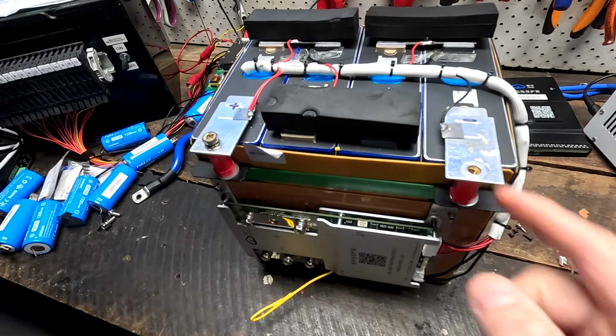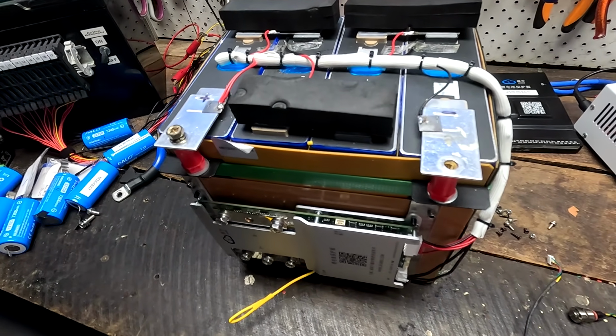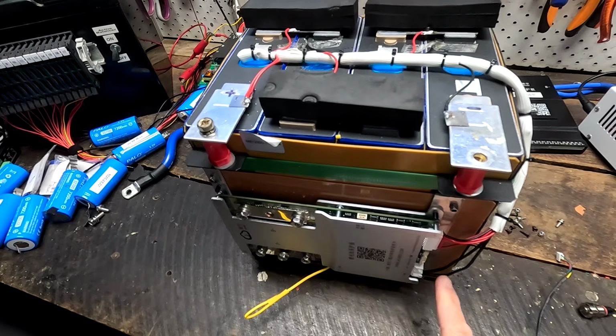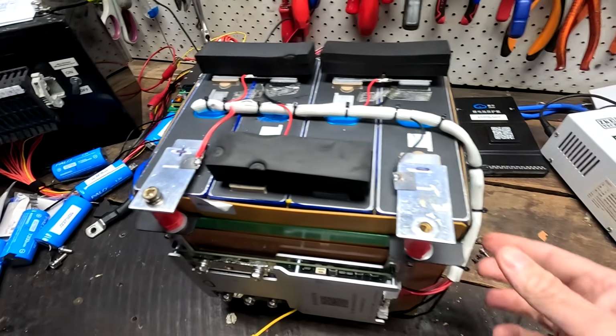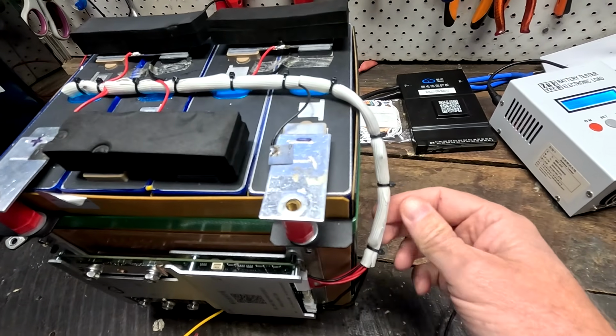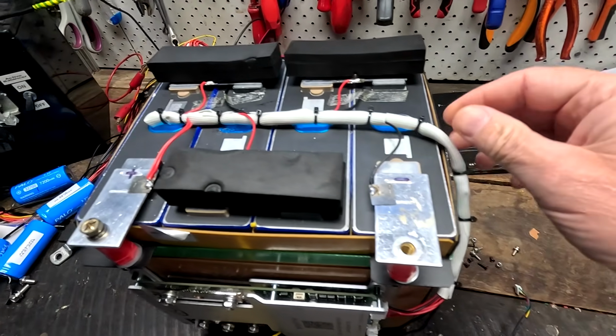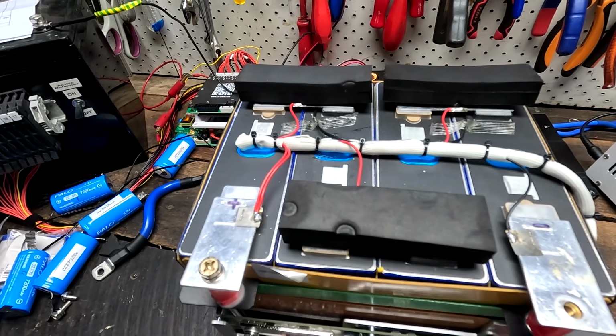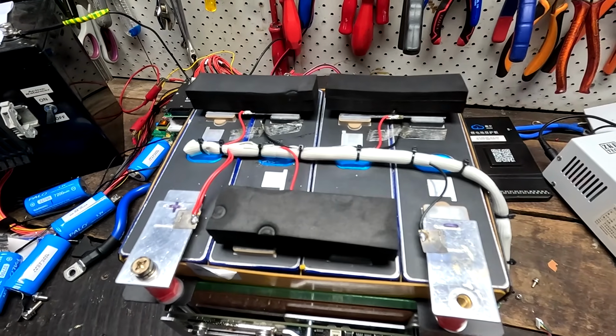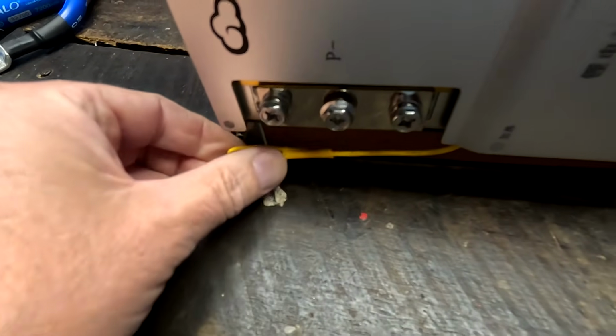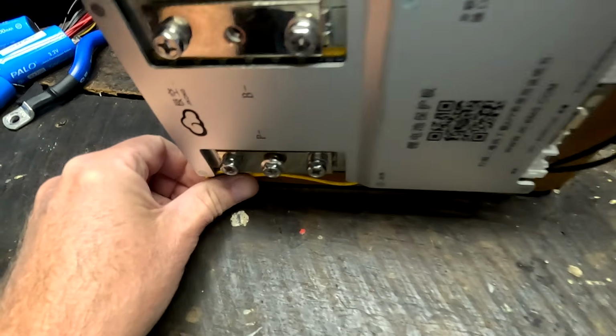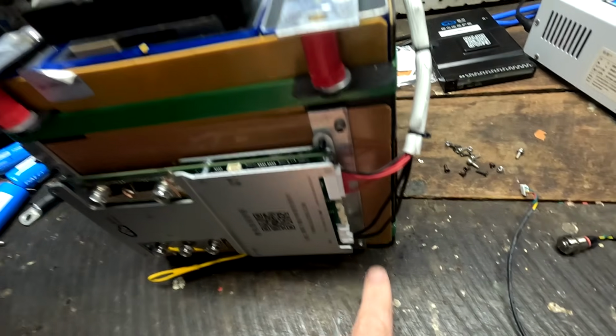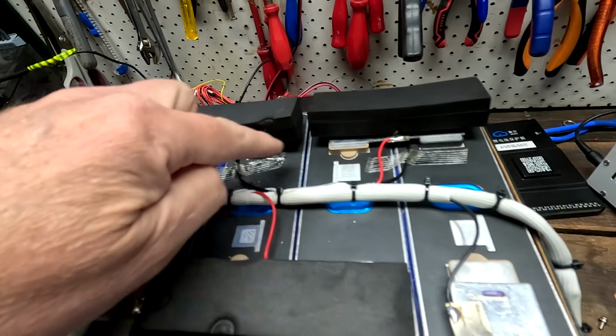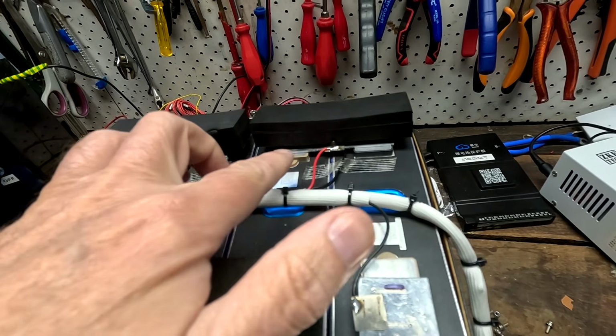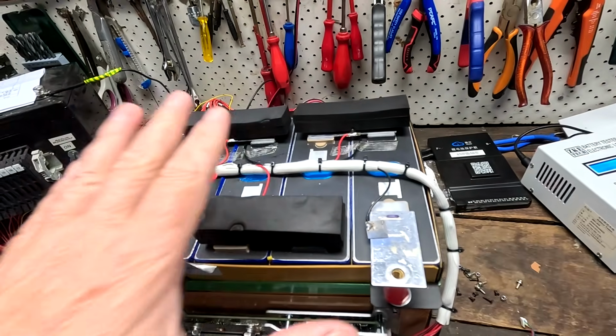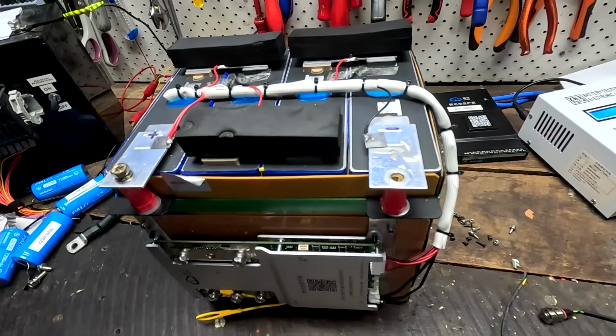So after testing all the balance cables and making sure the voltage order is correct, I've connected everything back to the BMS, using some of this heat resistant fabric which was around the balance cables already in the old setup, and cleaned this up a little bit here. I isolated the heating port, which we don't need, so it will just stay underneath here. Connected the two temperature probes, which are sitting over here, measuring the temperature under the bus bars basically. So everything is ready to go from this side.